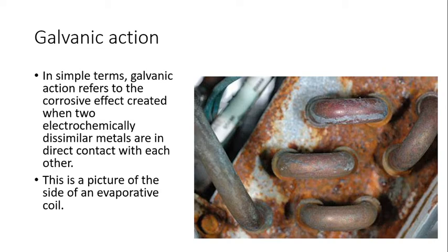before that happens. New systems are all made with tinned metal, so on the ends, if it's not already aluminum, on the ends of the coil they dip it in a tinning solution and they seal it completely so you don't get the moisture to it, which would cause this to happen.